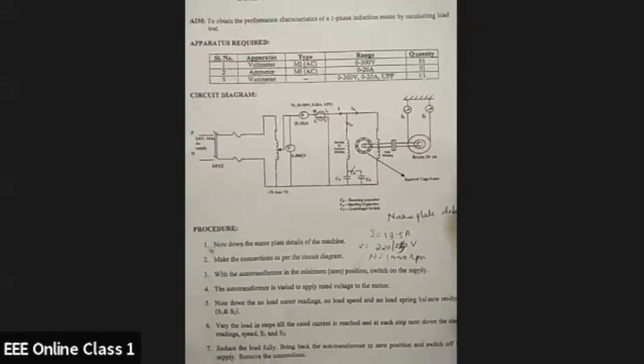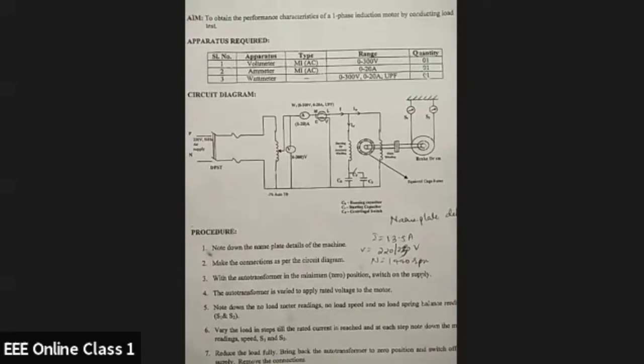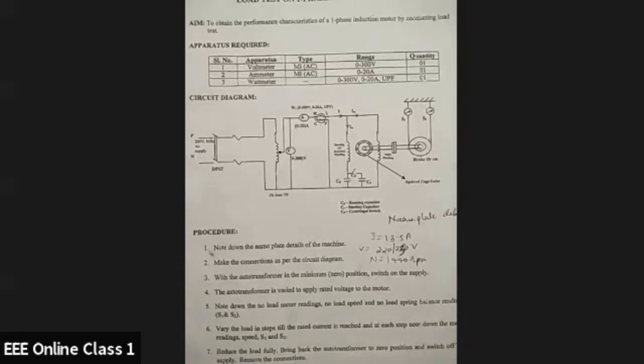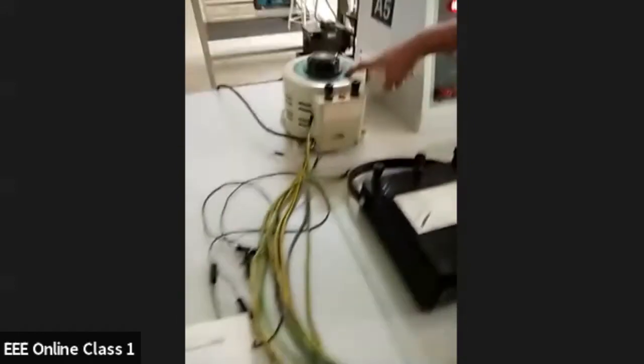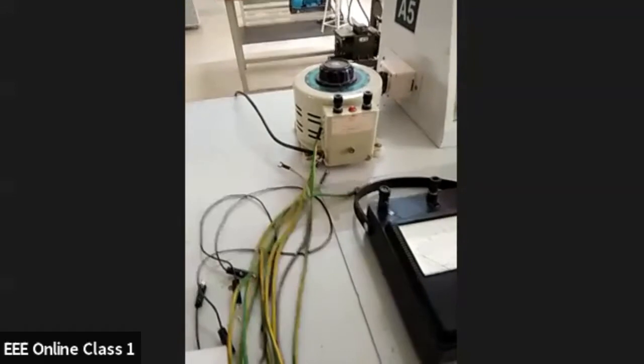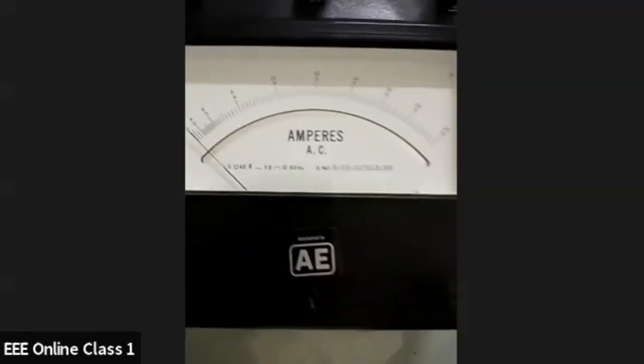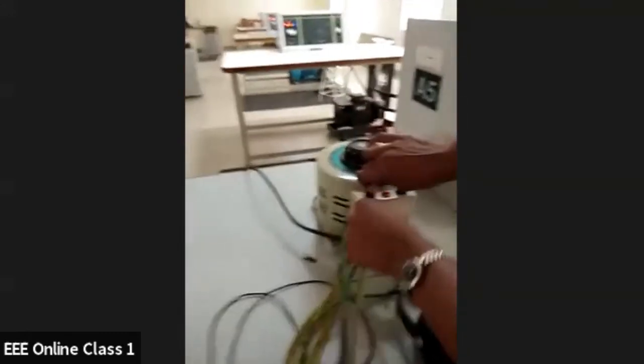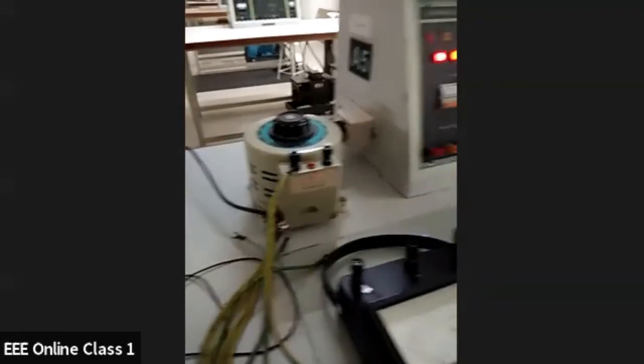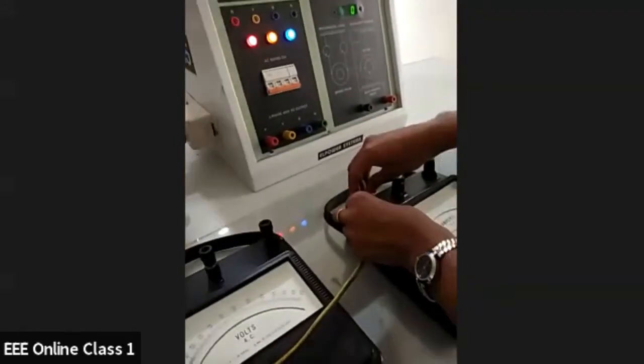Here is the circuit diagram for conducting the load test on a single phase induction motor. Let us see how to make the circuit connections. We require an auto transformer, a voltmeter of 0 to 300 volts AC, an ammeter of 0 to 20 amperes AC, and a wattmeter to measure the power of the single phase induction motor. To start with the connections, we take the connection from the positive of the auto transformer. This has to be connected to one of the terminals of the ammeter. Because this is AC, the polarity doesn't matter. So I'm just giving the connection to the common terminal.